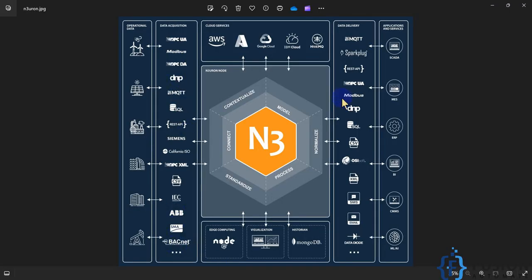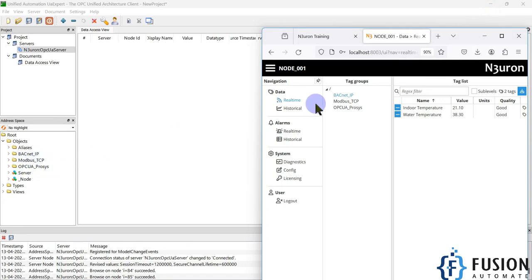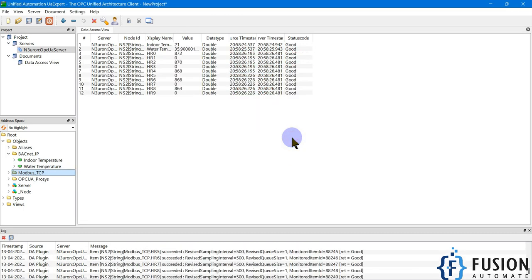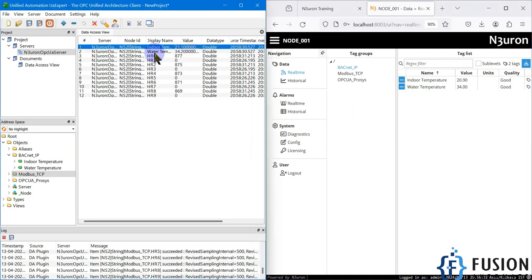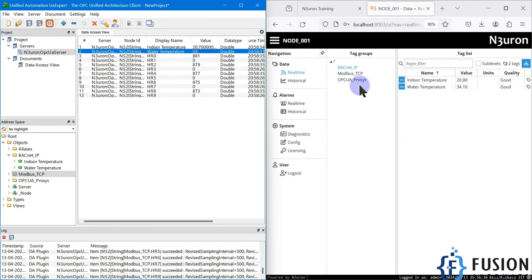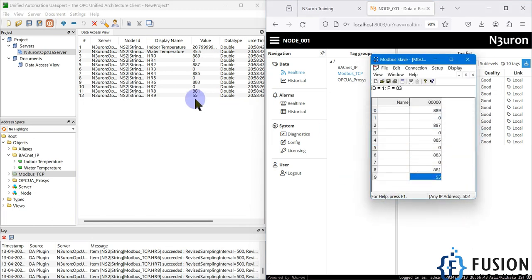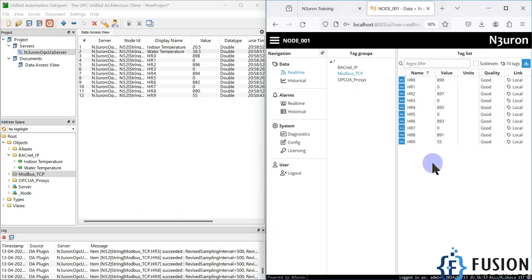We have successfully converted BACnet data to OPC UA. Any SCADA system, MES, ERP, or other system can now read BACnet device data over OPC UA protocol. Similarly, the same system can read Modbus TCP device data over OPC UA. I will drag and drop the tags — indoor temperature, water temperature — and also drag the Modbus TCP folder to view them side by side in real time.